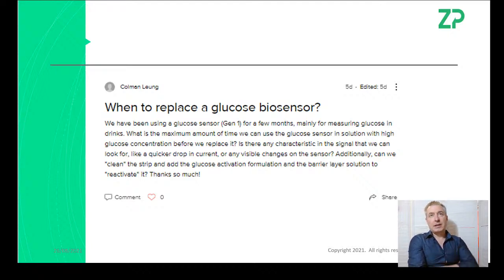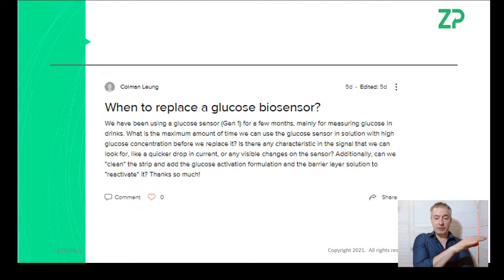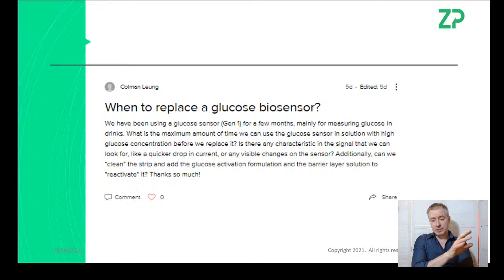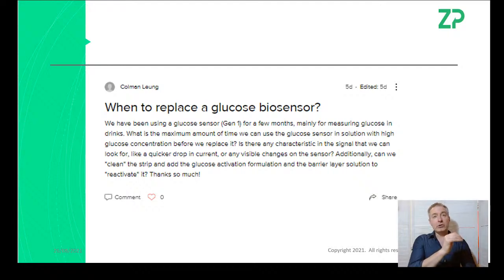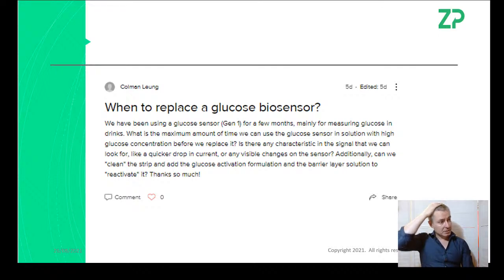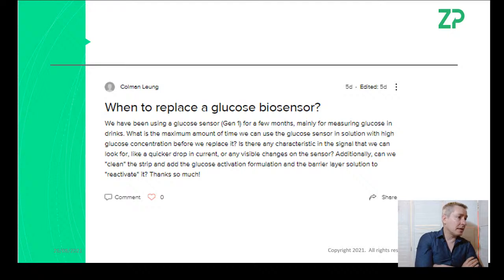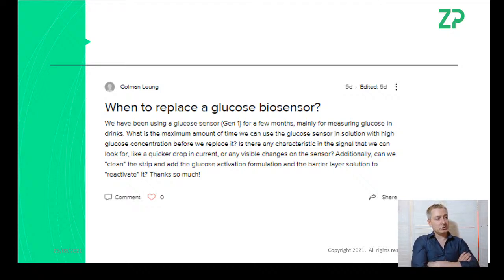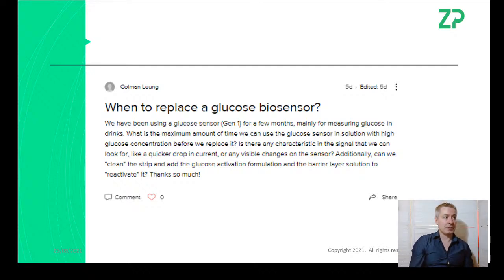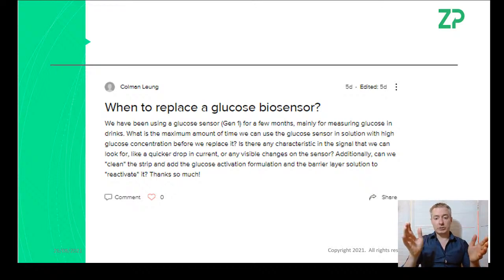If the enzyme layer degrades, your apparent sensitivity decreases, your linearity decreases, and you stop responding to glucose above certain concentrations. Typically you want linearity from 0 to 20 millimolar (about 0 to 360 mg/dL). As the enzyme degrades, linearity may shrink from 0-20 mM to 0-15 mM then 0-10 mM. Ali asks about signal drift in long-term use - I suspect signal drift may also be a manifestation of sensitivity loss.